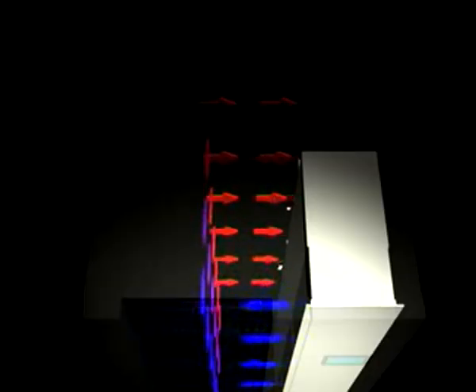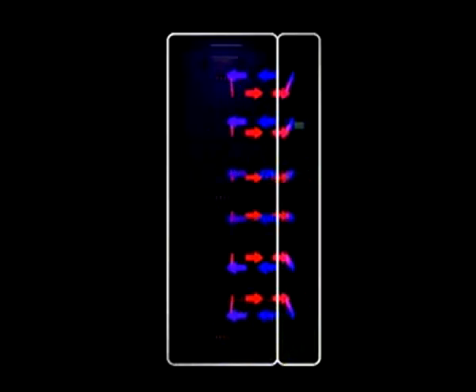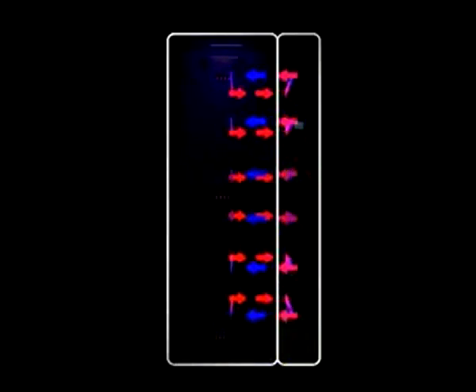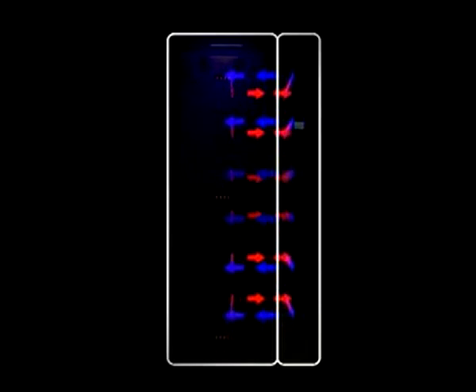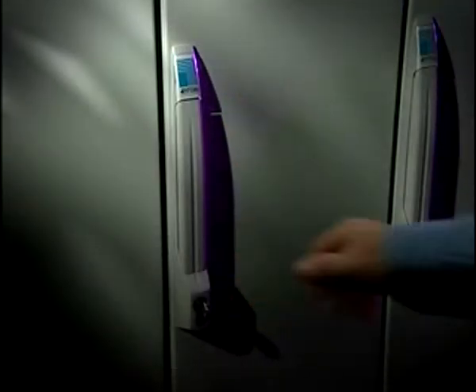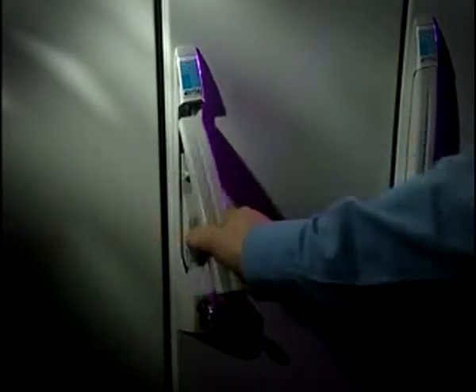The fans that push the air through the heat exchanger are fed from a single 3-phase supply, 2 fans per phase. Therefore, in the event of a phase failure, 2/3 of your fans are still working. The remaining fans will automatically speed up to compensate for the 2 that have shut down.